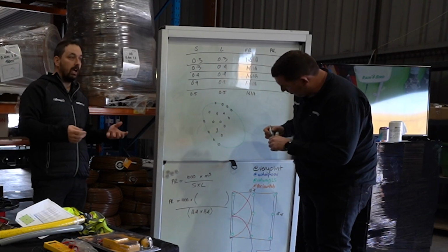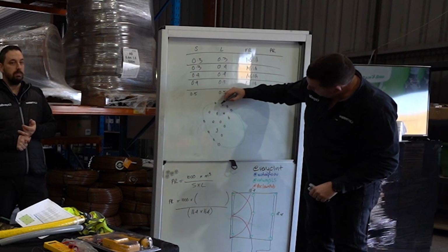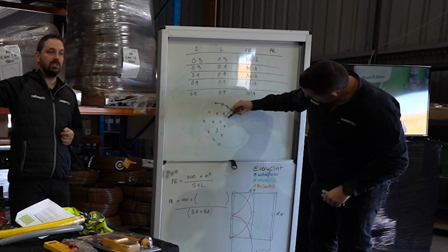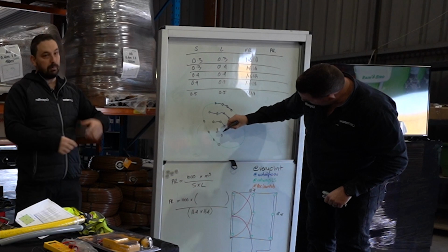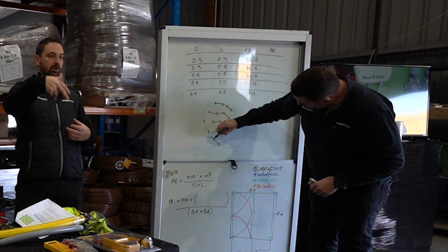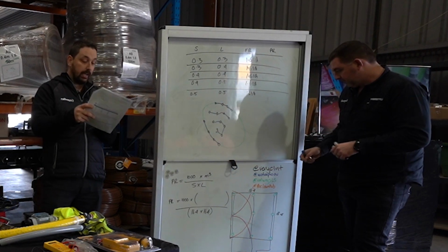And you guys would see that. Again, that happens not so much at new design stage, but over the course of a 10 to 15 year old system, where you're going out there and you've gone, I've busted a sprinkler, go back into my tub and grab a sprinkler out and chuck that back in, and there's no thought given to what nozzle's in there.